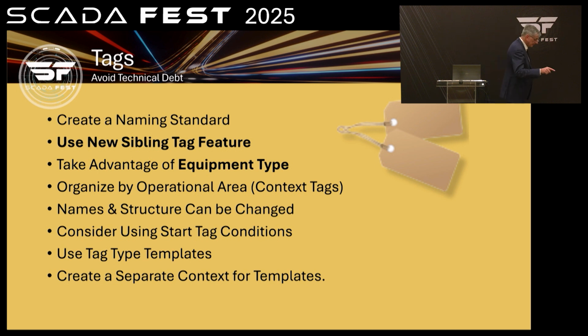Since you're templating, it's best to keep a copy of the master template in a separate folder, maybe a context you call templates. That's because any template instance, if you change one and hit update, will change all the others. But if you keep the base one in its own context, you don't modify it directly. You can then add or modify any individual instance to override parameters for that instance, without making that one the generic template. Keep the templates folder clean, and you can disable them there so they don't eat up any of your I/O tag count.